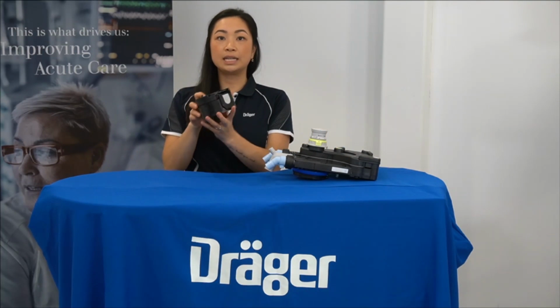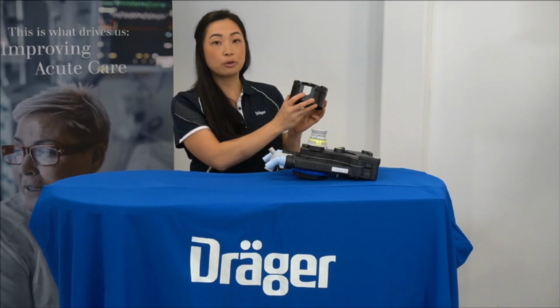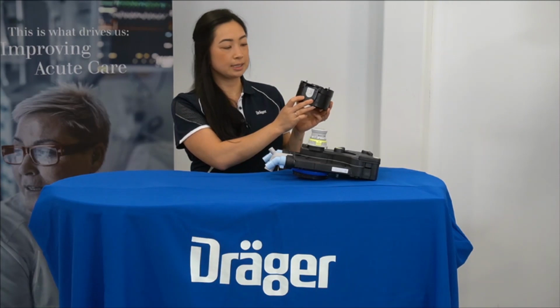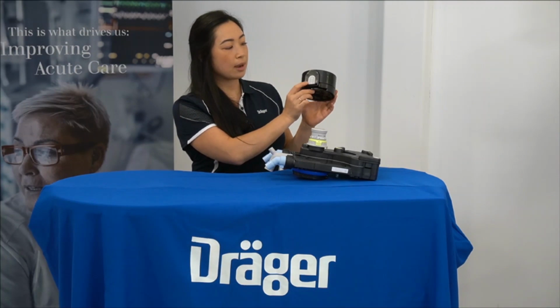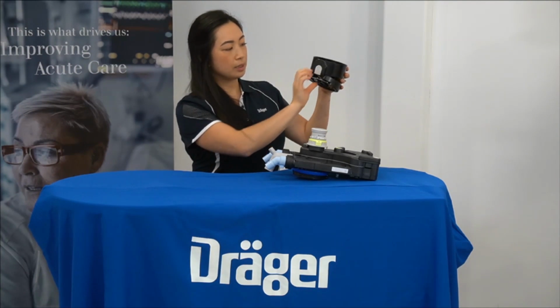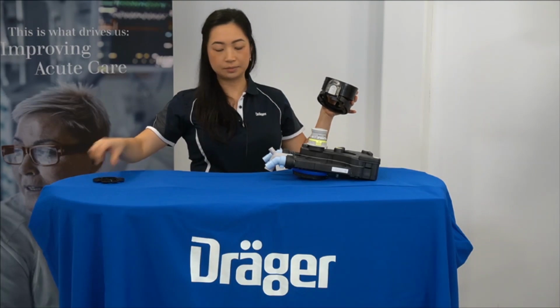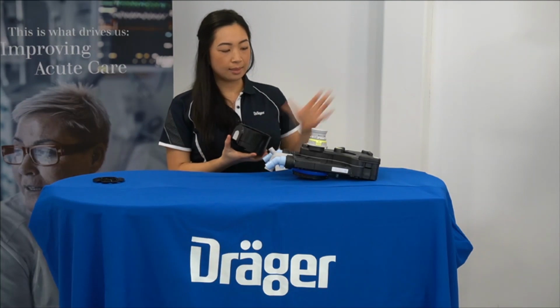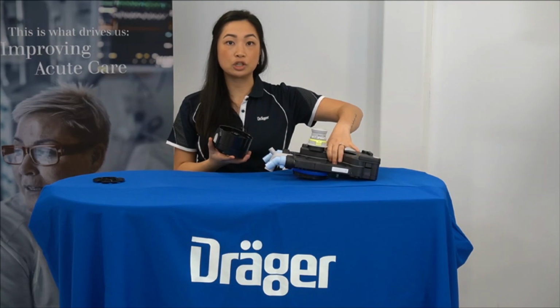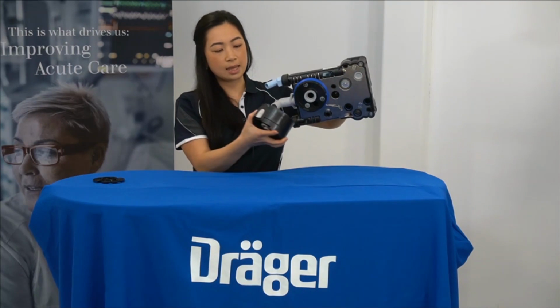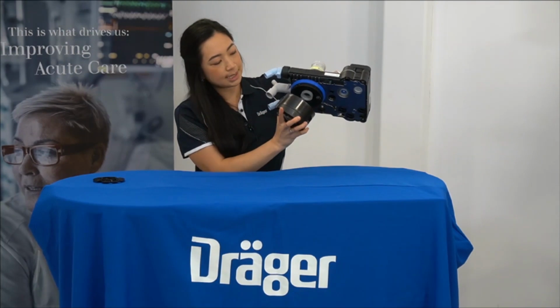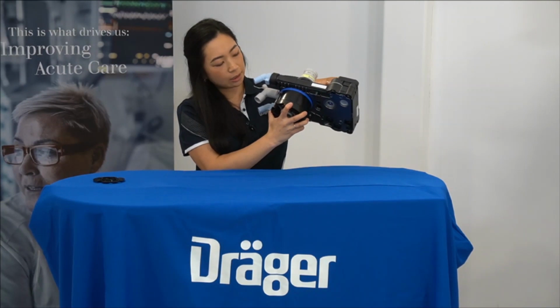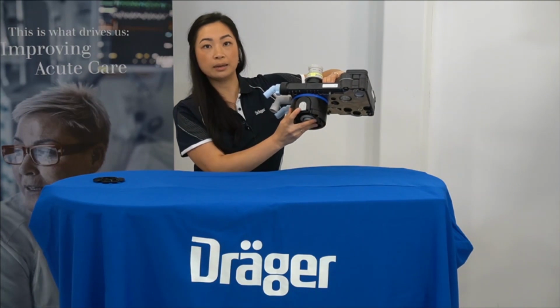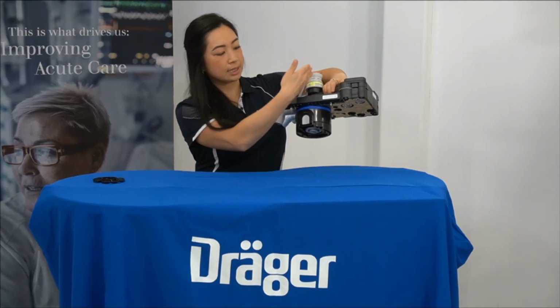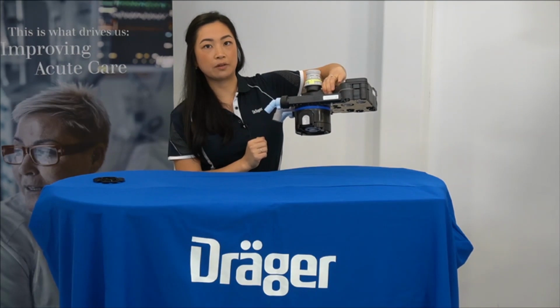Then to reattach the click adapter, remembering to remove the cleaning plate first. This is done by pressing the grey button on the click adapter and sliding the plate out. Then with one hand firmly on the top of the breathing block and the other on the click adapter, starting off centre and turning so that the grey button ends up in the middle underneath the dot on the APL valve.